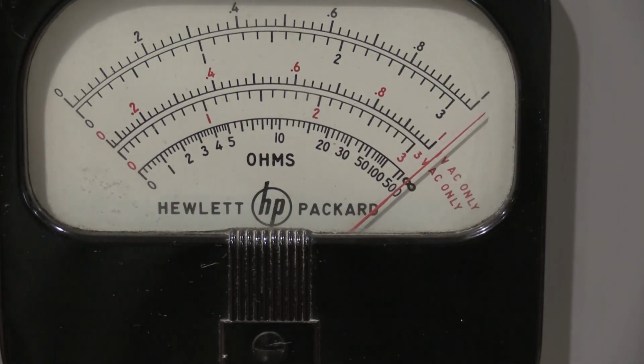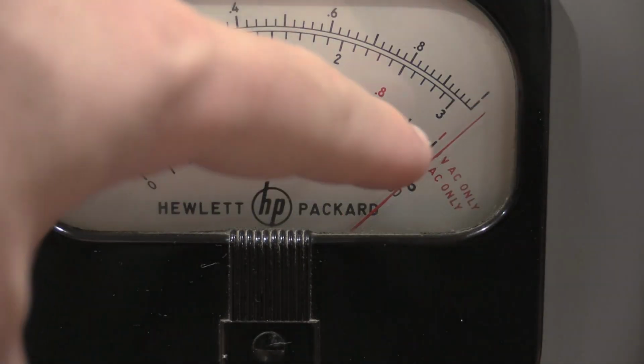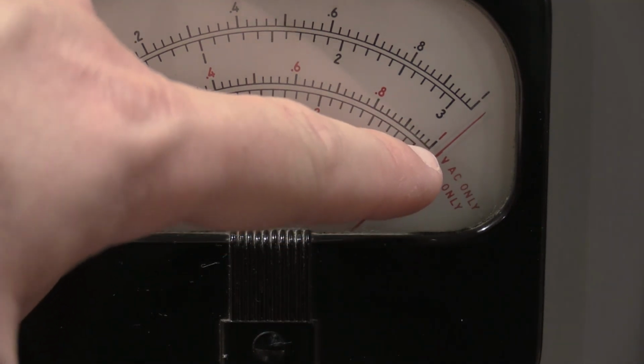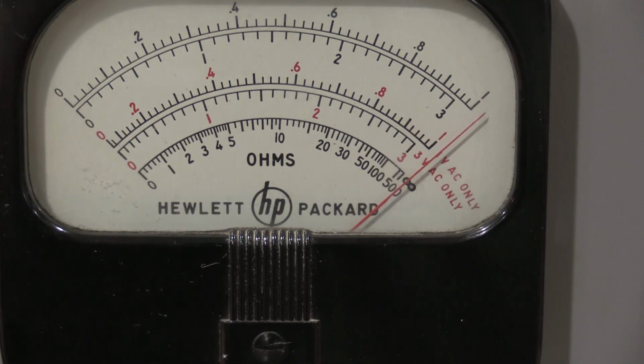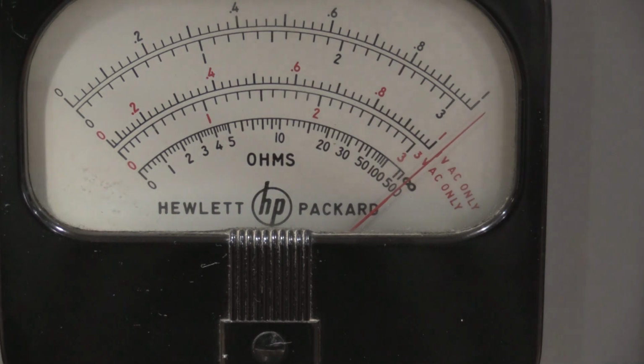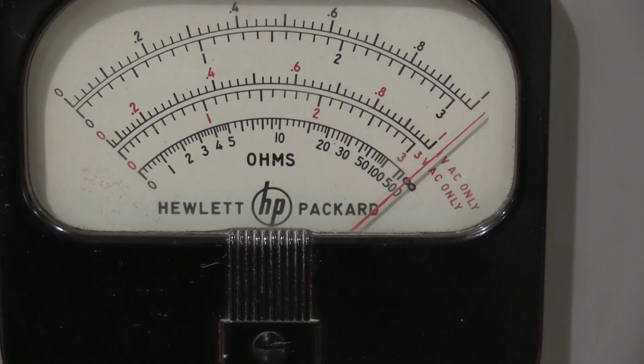Okay, I have everything set up to dial up the 1 volt AC. Now the scale I need to use for the 1 volt AC is down here, and we need to line it up with the 1 right there. So I've already got the tuning tool put in. I'm monitoring the 5200A with the 7510. I've got the 5200A phase locked to the 4192, which is then tied to the rubidium, so I'm getting the stability. And I'm also monitoring the 5200A with the Agilent 53131A, just to keep an eye on the clock, make sure it doesn't go too crazy.